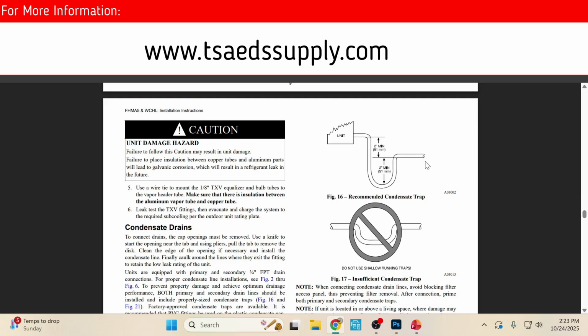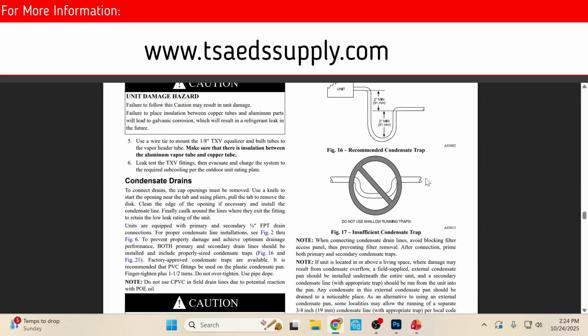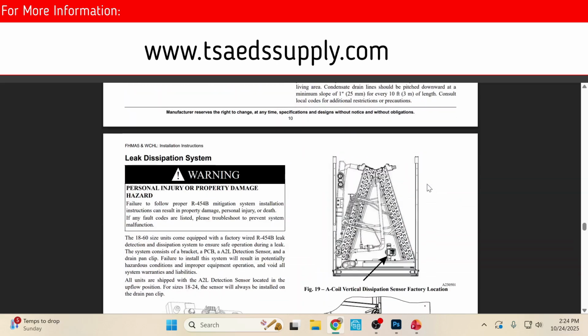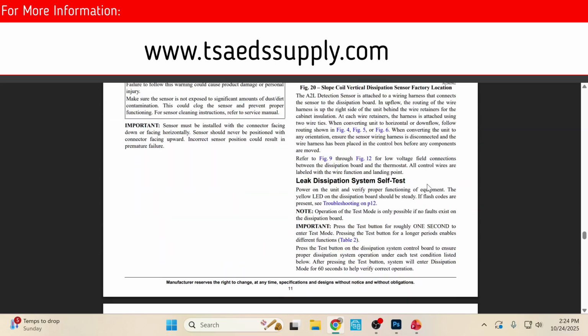If you're working on any of the ICP equipment, and I'm sure other brands do the same thing, if the line is just dripping, you got an airflow problem, or you've got where the drain can't breathe. So understand that you want it to pee just a solid, steady stream of water. The more water coming out of that drain, the less humidity that's going to be trapped inside the house. So keep that in mind. But I want to work our way down.